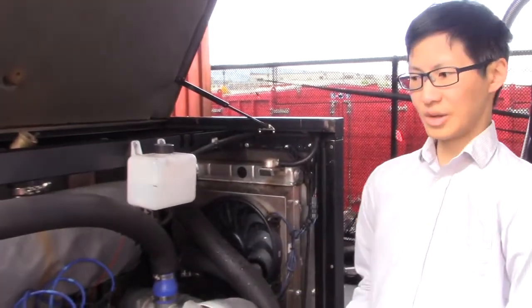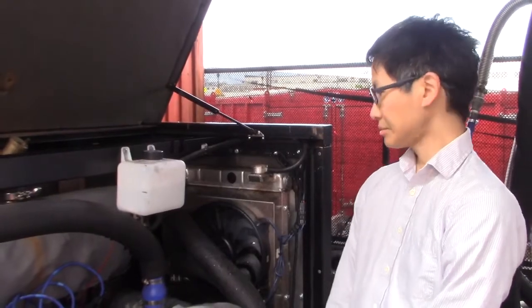So by that means the Power Pallet is able to provide 2 kilowatts thermal in the form of hot water for every 1 kilowatt of electrical load. Now the thermal output is tied to the electrical load because it's based on waste heat. You can't just produce hot water independently of the electrical load, but as long as you're generating electricity, there's sufficient heat to power the CHP system.